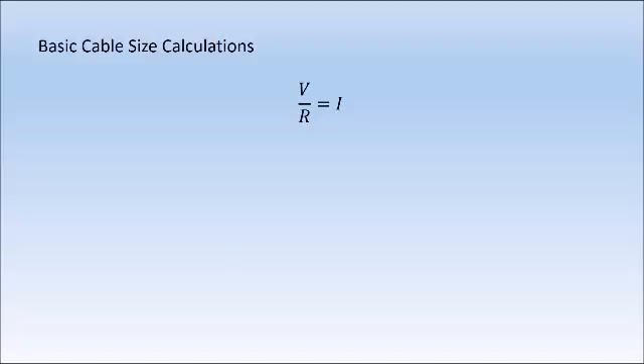Before we go into that, let's look over some basic cable size calculations. The formulas we're going to be using are: voltage divided by resistance gives us current, and power divided by voltage also gives us current. The reason I've picked these two out is that when we're selecting cable sizes, current is important. The current draw on that circuit is important — the higher the current draw, the more electrons are flowing within our conductor, and the higher the temperature gets within that conductor. Manufacturers specify current carrying capacity for their conductors or cables.